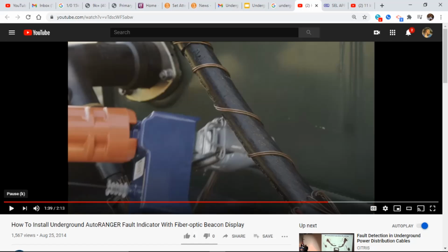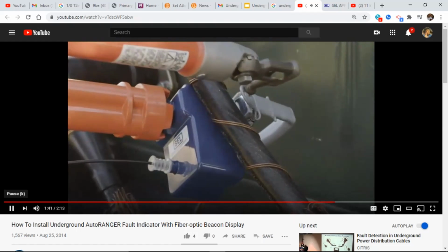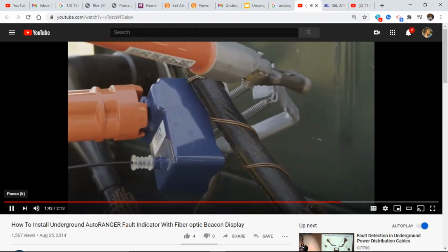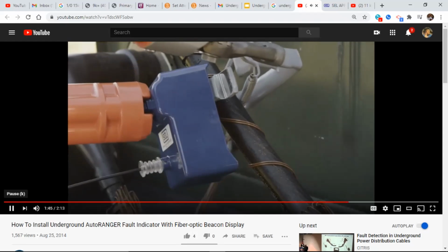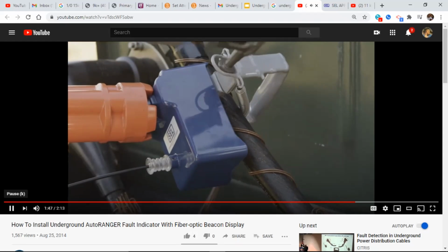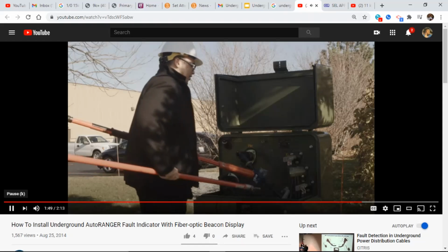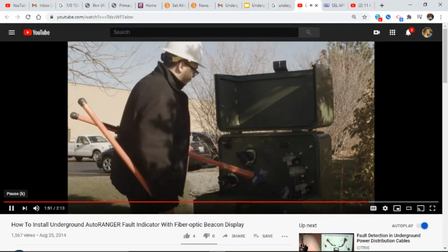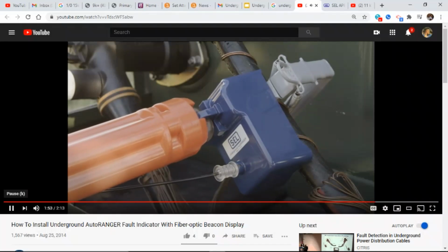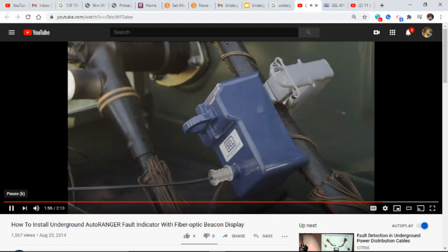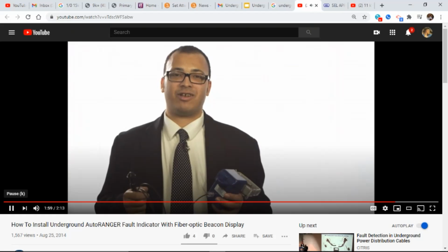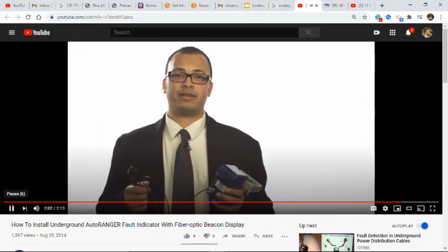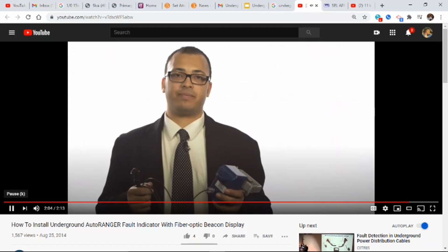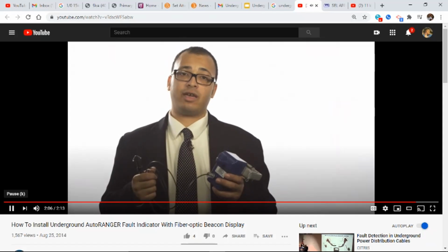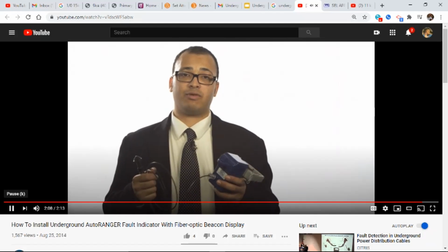Up to the cable, reach around with my other tool, and open the core, positioning it around the cable, and then locking it into place back over the core. I can now remove the hot stick tool from the product, and I've installed the product onto the cable. So now you've seen how easy it is to install the Underground Auto Ranger with fiber optic display on an underground cable. You can use this sensor today to locate faults on your system and improve reliability on your circuits.